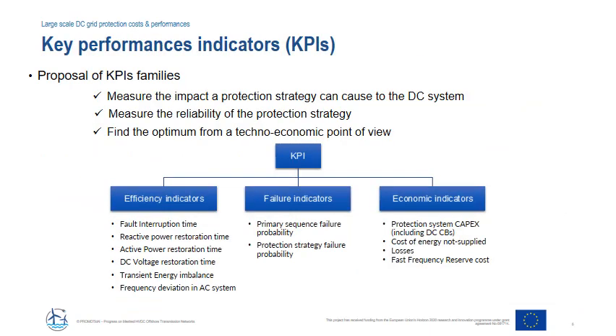The proposed methodology relies on the calculation of a set of key performance indicators. Here is a brief recap on those indicators. Efficiency indicators measure the impact a protection strategy can have on the AC/DC system. They assess to what extent the performed protection sequence is able to limit the impact of DC contingencies on the interconnected AC/DC system. Failure indicators measure the reliability of the protection strategy by giving the probability that either the primary protection sequence or the backup sequence fail to clear the fault. Economic indicators estimate the cost of the protection strategy and, combined with other indicators, make it possible to find the optimum strategy from a techno-economic perspective.